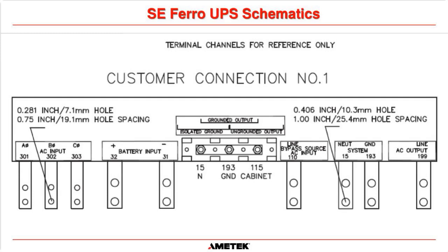So therefore, for your bypass, there's going to be a transformer for your bypass. Actually, let me do it down here. There's going to be a transformer for your bypass, which then feeds in here and then up to your neutral. And then at the secondary of the bypass transformer, that is where you're going to have your ground connected. So if your ground is connected at the secondary of the bypass transformer, that means you do not want to connect another neutral to ground here, because then that's a secondary point and that will allow circulating currents. Okay, so in 95% of cases, the only bus bar that's going to be connected is the ground to cabinet connection within your UPS. Okay.